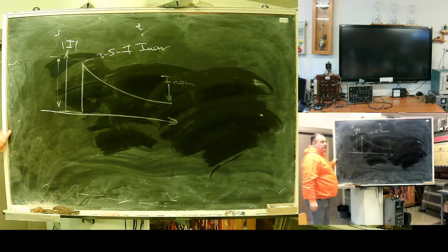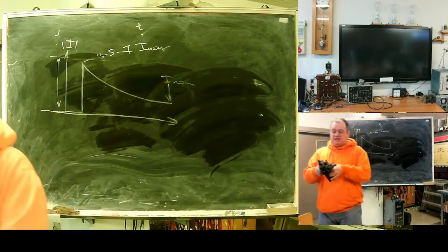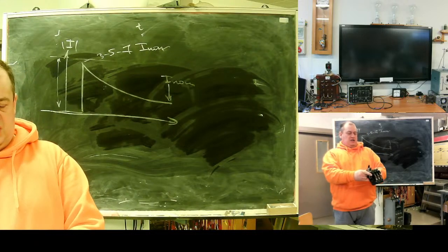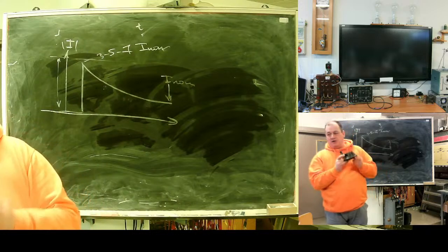This is the operation current for the instant part. Here I can adjust starting from 6 up to 10 times nominal current.